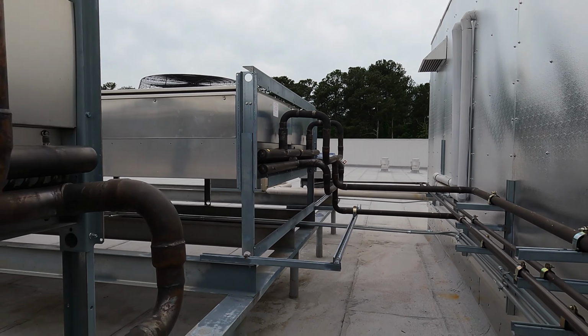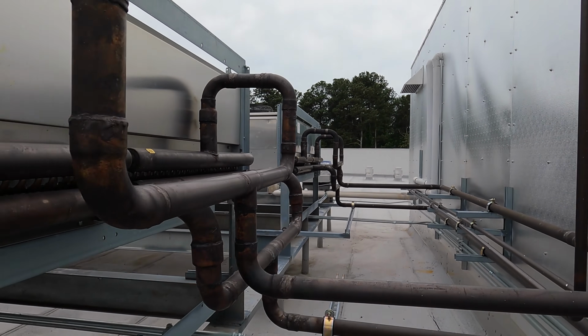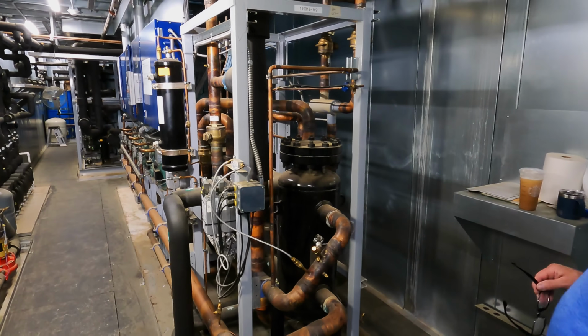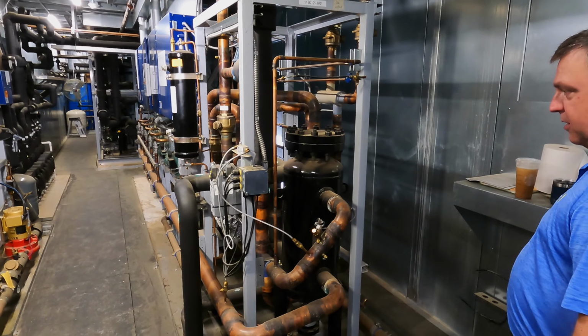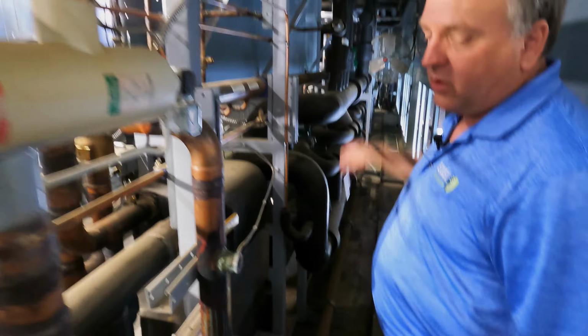We want to keep it in the system. So we split it during low ambient conditions. When we get below 50 degrees, it's going to energize the solenoid to go to ambient conditions. We'll go back in the front, and you can see where it enters the receiver. And here it is, the inlet of the receiver.